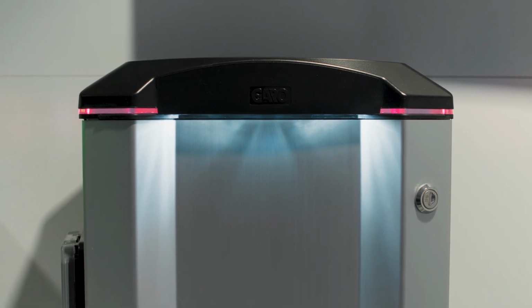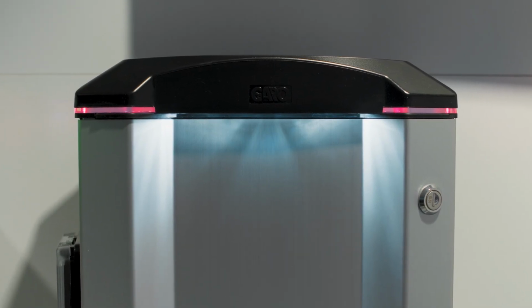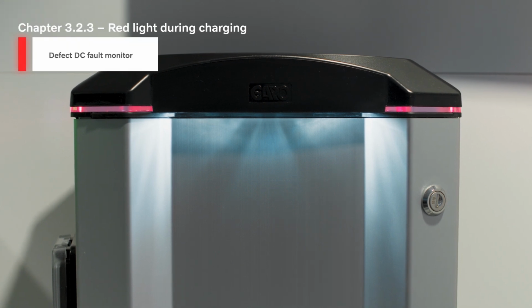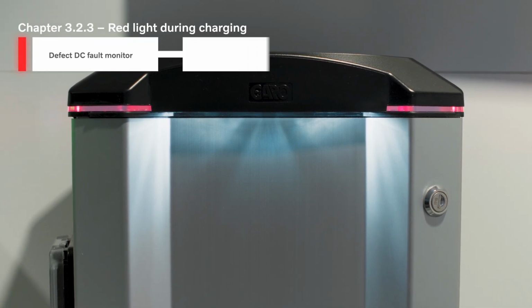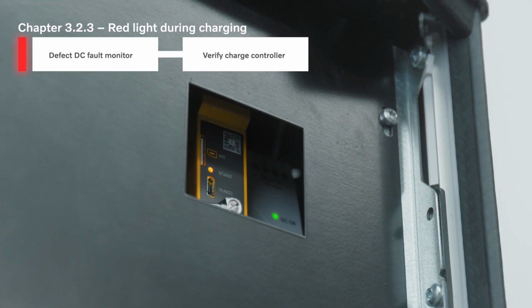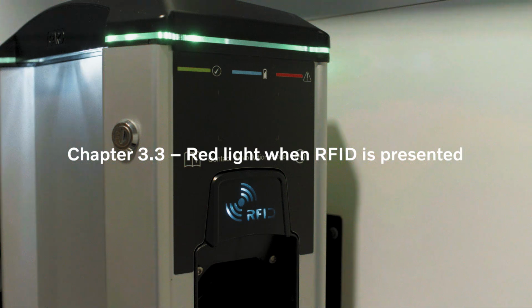A firm red light that appears during charging will also appear if the DC fault monitor is defective. Check the charge controller. If the orange LED indicator on the charge controller is firmly lit, then the charge controller needs to be replaced.